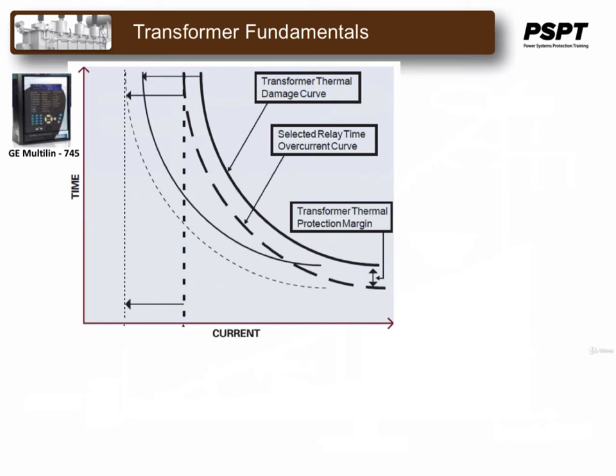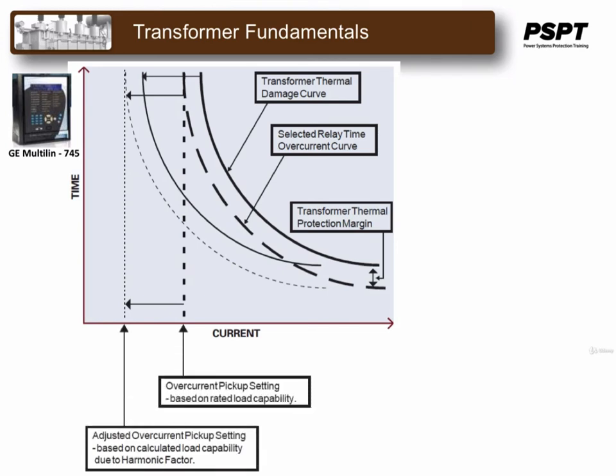The 745 can be used to provide backup protection for the transformer and adjacent power system equipment. Instantaneous overcurrent elements can be used to fast clear a severe internal fault or external through faults. Timed overcurrent protection elements per winding allow coordination with adjacent protected zones and act as backup protection. Timed overcurrent protection functions are provided for phase and ground currents. A variety of standard time current curves and definite times are provided, as well as flex curves to coordinate with adjacent protections, including fuses, as well as transformer damage curves and thermal damage curves for downstream equipment.